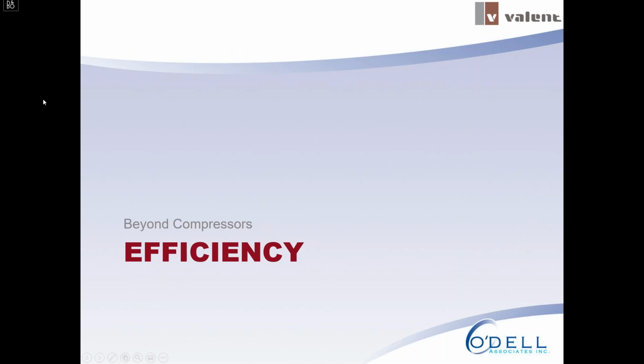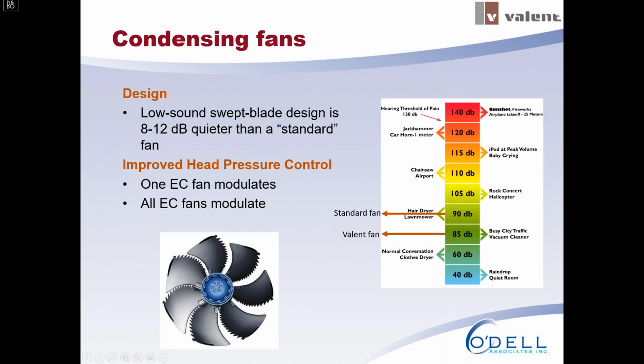We talked about compressor efficiency options, but another major way to improve the efficiency of a refrigeration system is with the condenser fan design and operation. Valent uses an owlet blade condenser fan, and there's a picture of it, and you can see it has serrated blades. It looks a little bit strange if you've never seen one before, but those serrated blades are really to help with efficiency of the fan and also for sound.